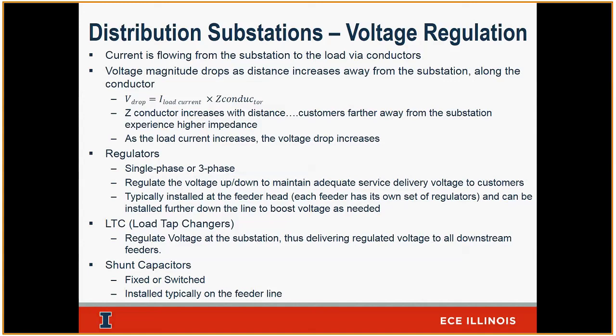Another tool is the LTC. Some of these transformers come with an LTC, a load tap changer. That does exactly what a regulator does. The only difference is that an LTC, because it's on the transformer, regulates voltage for all the feeders. So I lose the capability of controlling voltage per feeder. Now I have to control that entire bus. All these feeders are controlled by one unit, so I don't have the luxury of designing each feeder with its own optimal voltage point. So it has a little bit less flexibility, I would say.